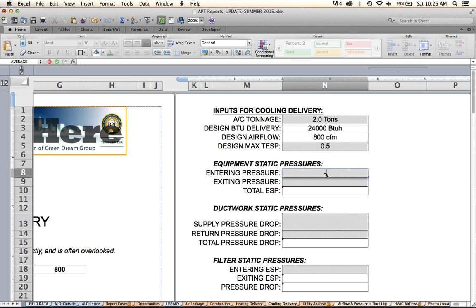Okay, so the way that we're going to do this is get the static pressure drops for three different things. We're going to find the total external static pressure, and then we're going to find the pressure drop for the filter and the pressure drop for the coil. This is going to give us a really good, solid, meaty amount of information. So if you know what I'm talking about at this point, then follow along.